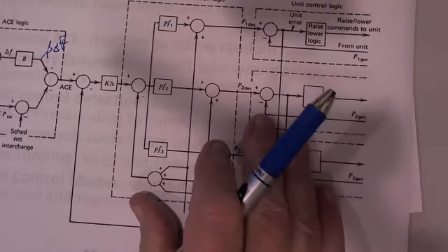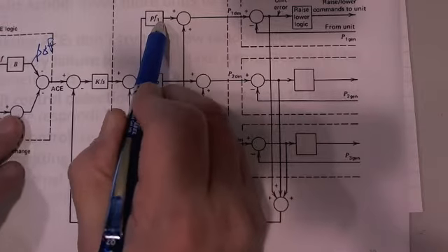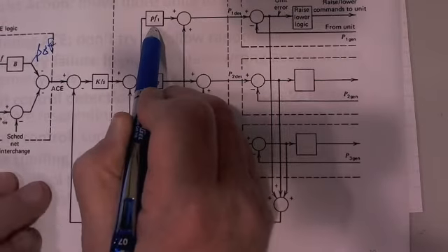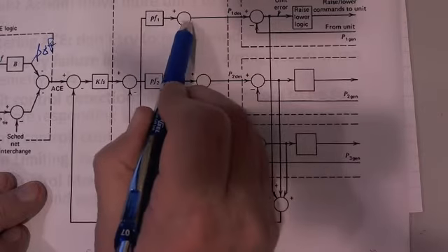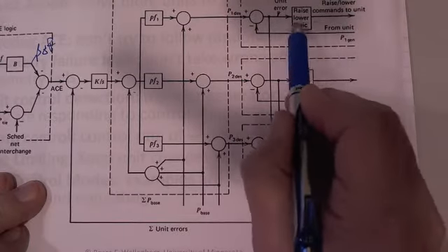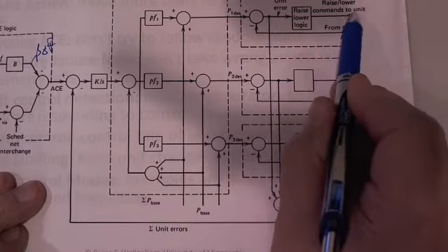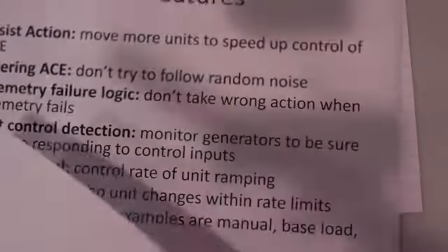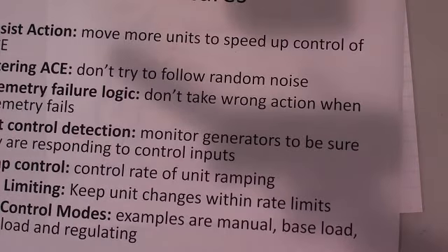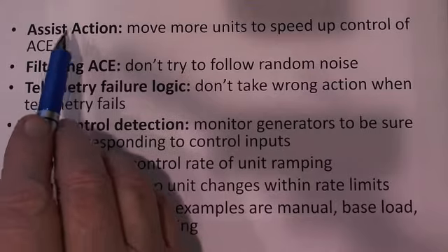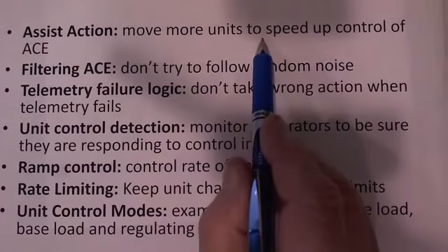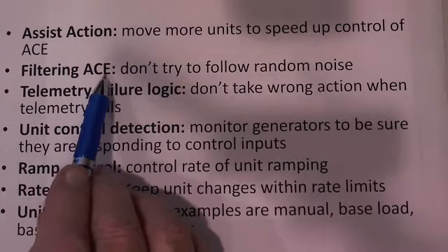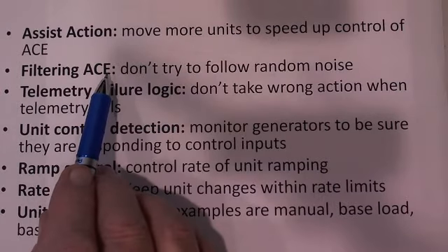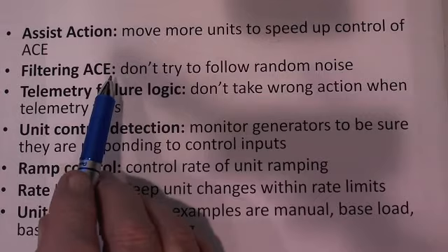And if you remember way back, we talked about something called a participation factor, and that's this factor here that allocates the ACE to each generator, and there's an individual control loop that says, you go to this point, and it sends that to its speed governor. AGC itself has a lot of features. These are some of the features that you would get: assist action, move more units to speed control, filter the ACE. They don't want the system to chase a signal that's going to come back.